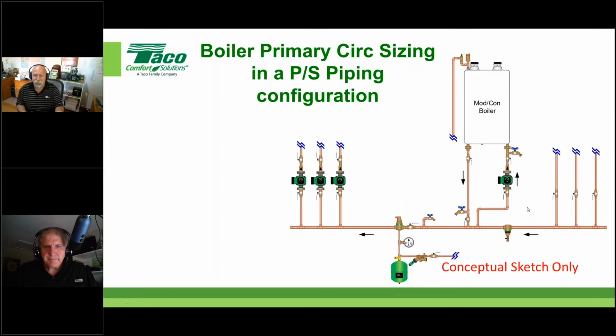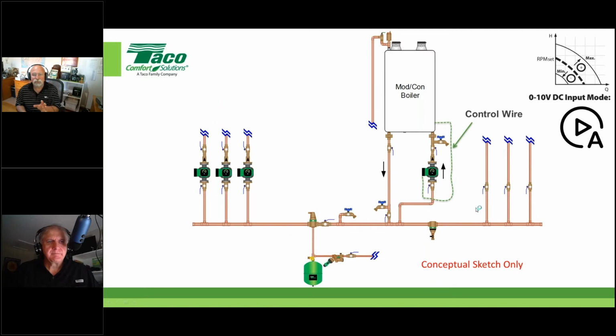Now, you've already seen this picture. John showed you this little sketch of a typical moose horn pipe showing a wall hung condensing boiler, circulator pumping into it, and this happens to show three zone pumps. So what we want to focus on is a couple of points here. This circulator sizing, as mentioned already, and this configuration here of the closely spaced tees. It's a term that we've heard quite a bit. I believe that's a Siegenthaler reference, but we're going to expound on that a little more so you feel comfortable with that.